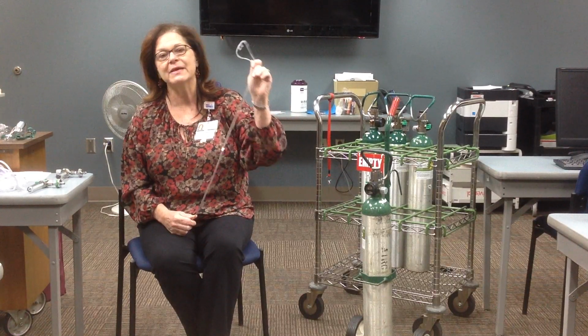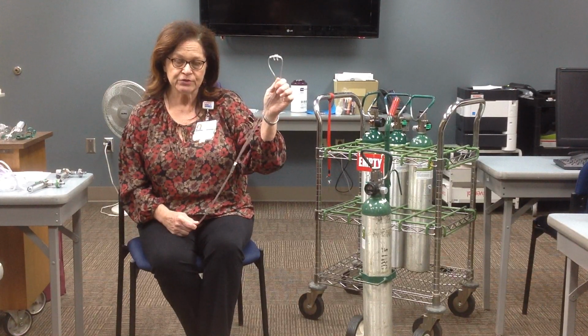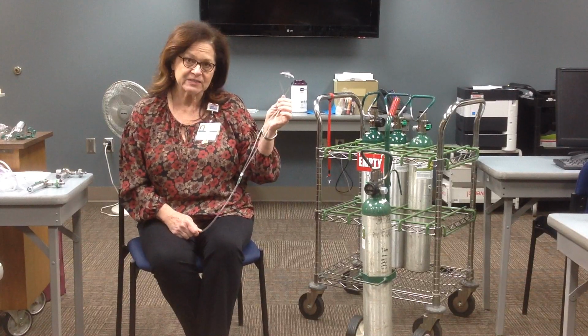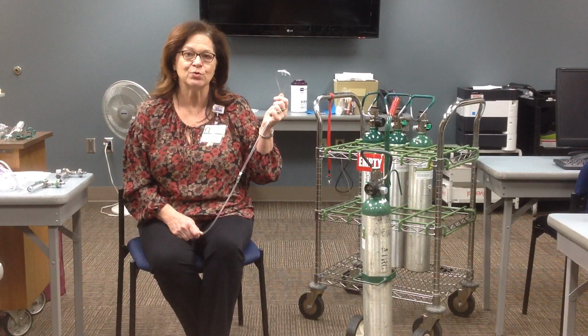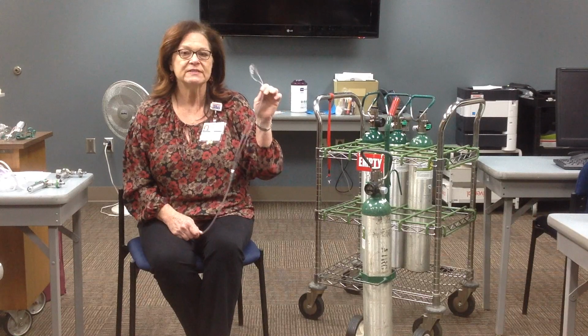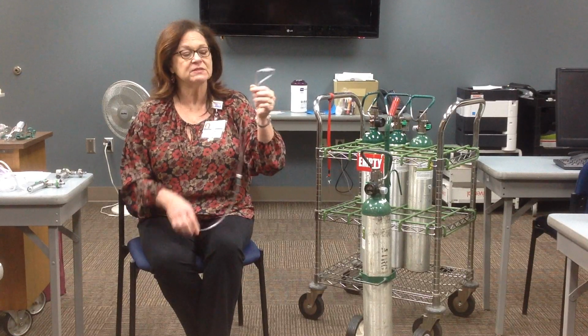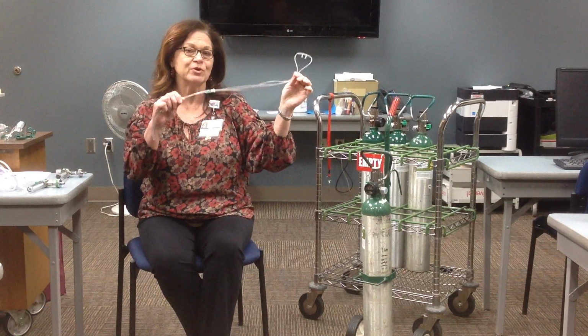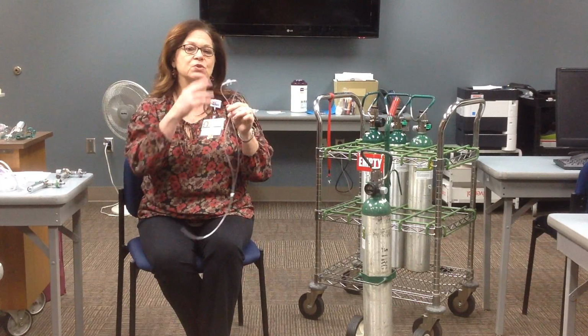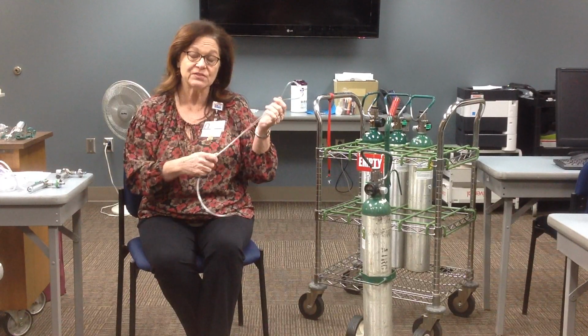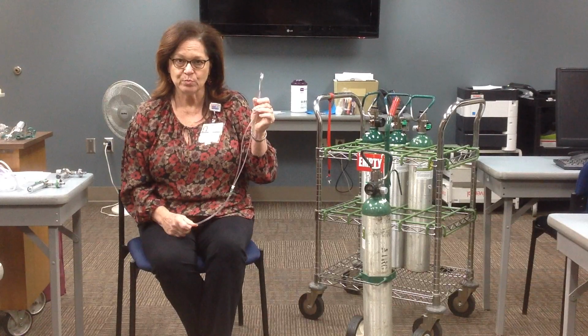It runs from 1 to 6 liters, never more than 6, because you can actually damage the nasal mucosa by increasing that greater than 6 liters a minute, because the lumen of this tubing, the diameter, is so small that it creates quite a turbulent airflow or gas flow, and it will damage the nasal mucosa.